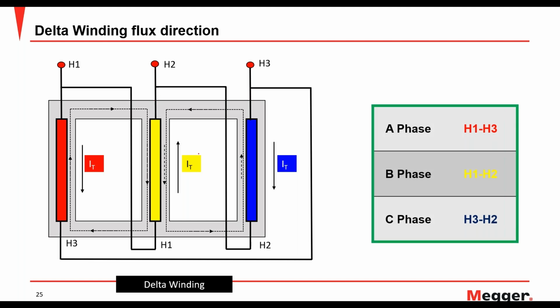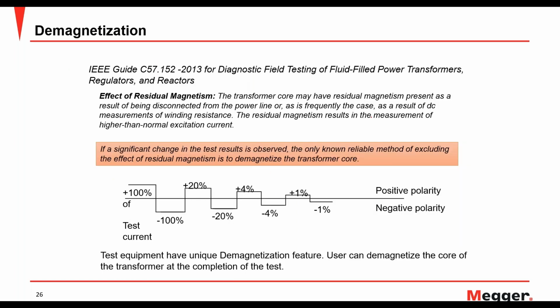This is for delta winding. Similar concept, just move in the direction of flux, not opposite to it. It will help you attain the saturation much faster. Now, whenever we perform a winding resistance test, which is a DC test, what is necessary after performing it? Demagnetization, right? Because your transformer is an AC component and you don't want to leave any residual magnetism inside it.